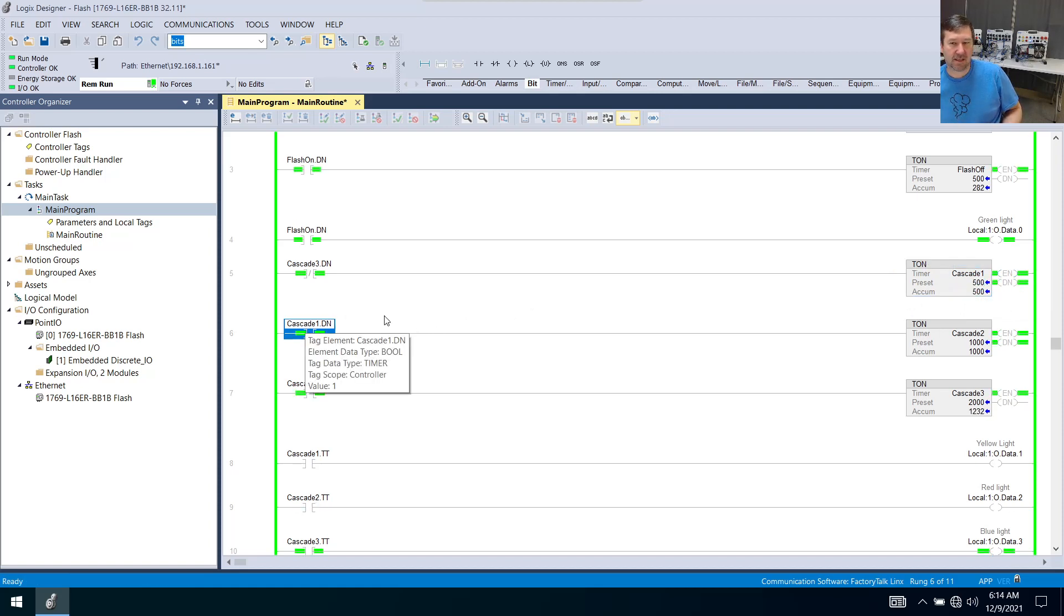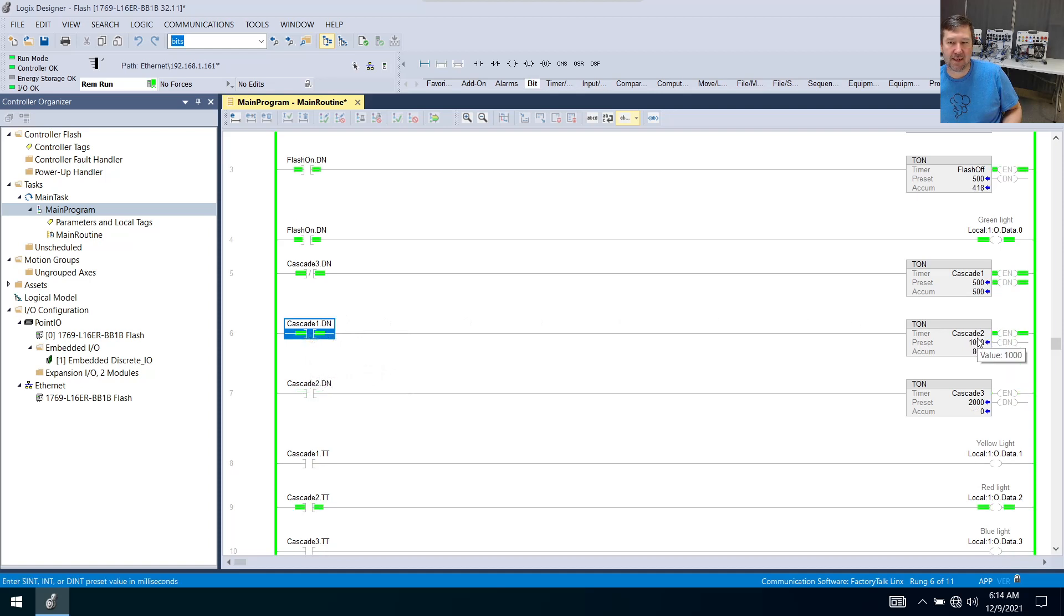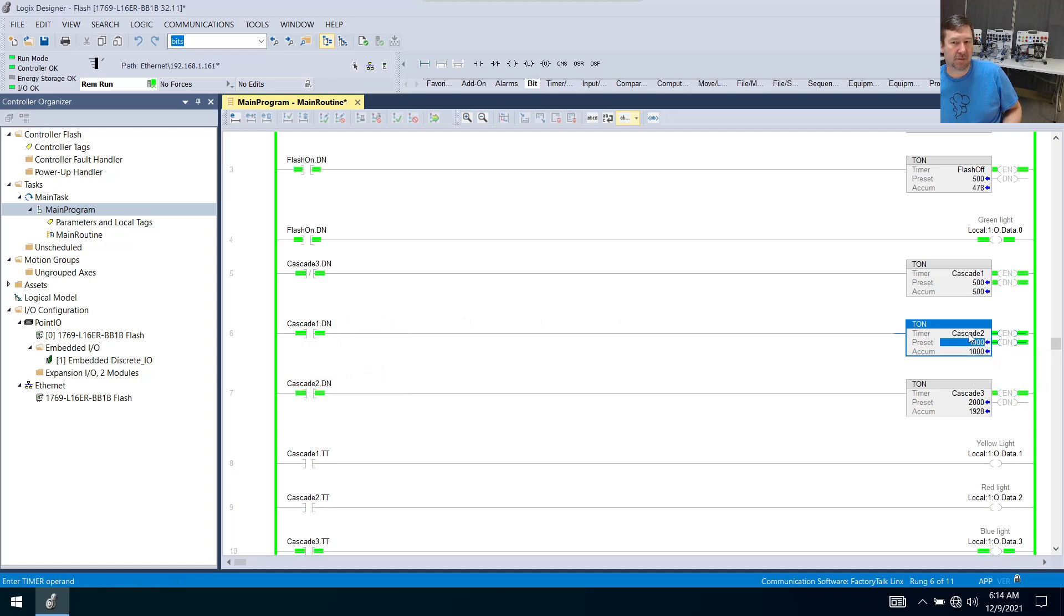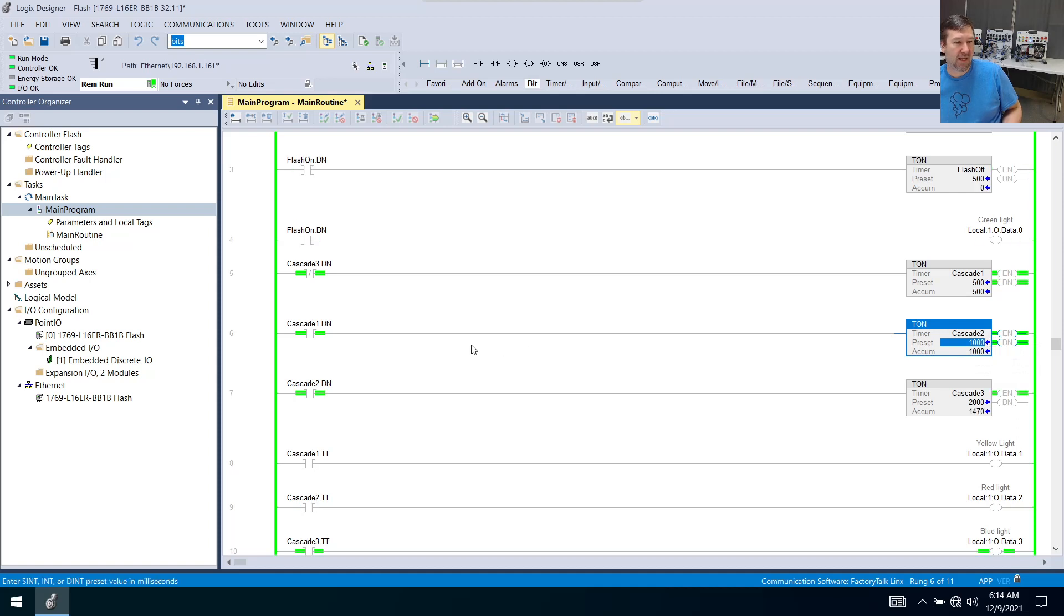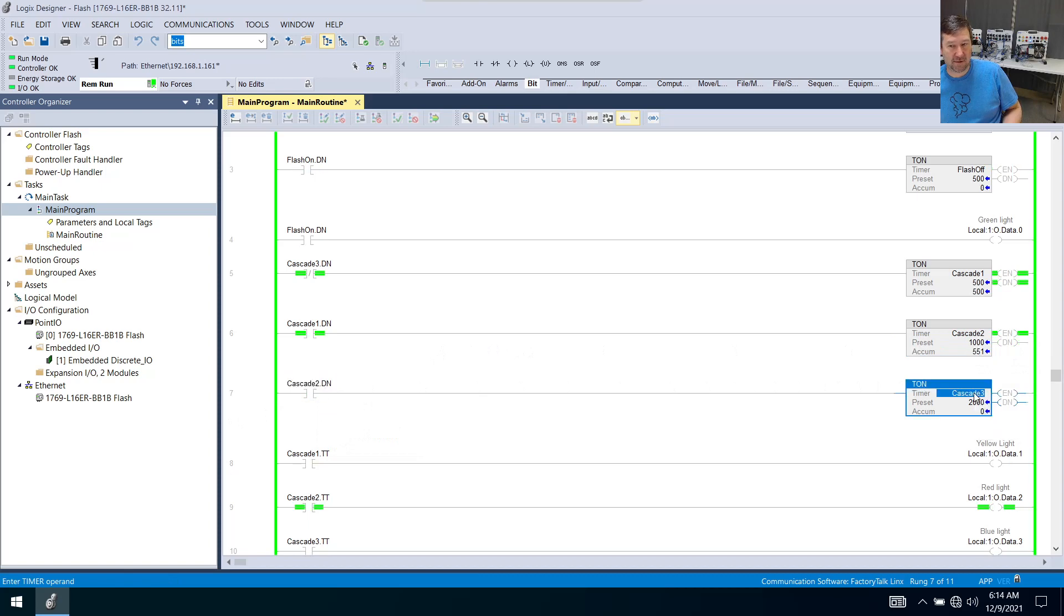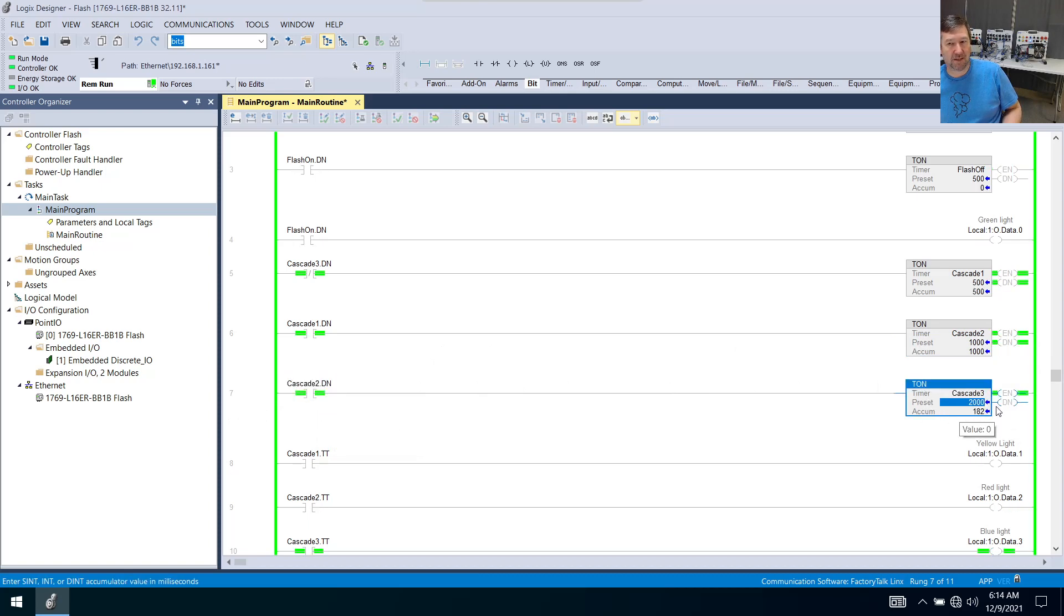It's going to be false. It's going to write a zero to everything except the preset of cascade two, including the done bit that is used for cascade three. So this goes false, it's going to write a zero to everything but the preset, which includes that done bit, which means now this done bit is a zero again. And this one becomes true. And it repeats the process.